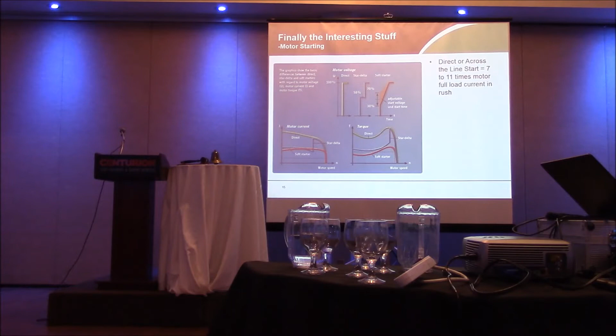If I start too big a motor on a generator, I get a frequency dip, I get a voltage dip, and what can happen with that is the electrical loads on the system will drop out. The voltage will drop low enough that the coils, the magnets that hold the starters closed, the electromagnets hold the starters closed, will drop out. Okay? Then all the motors stop. That's not good.